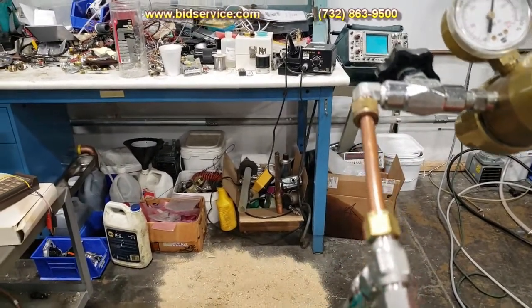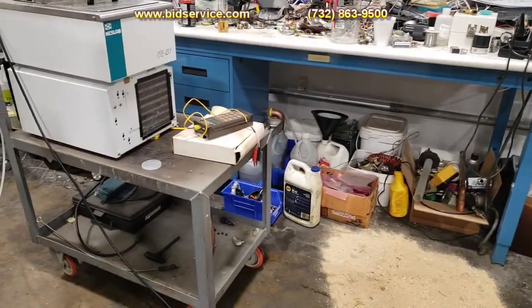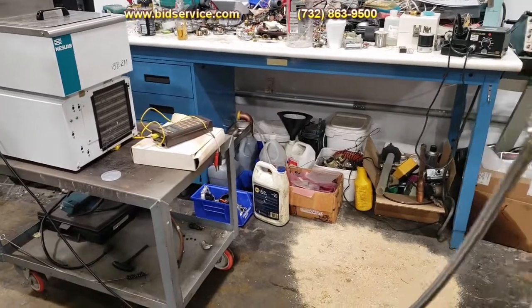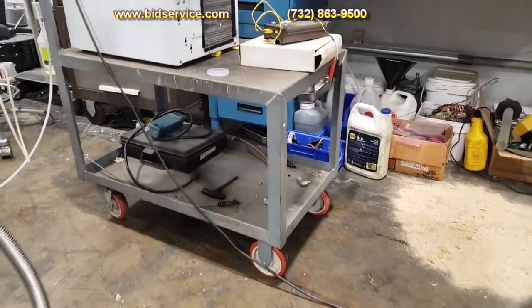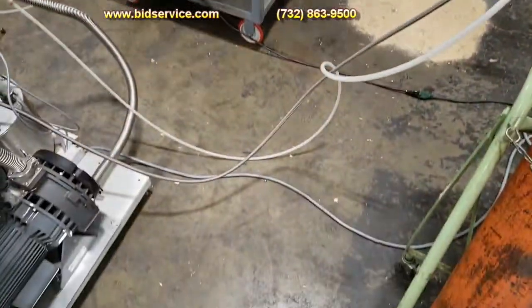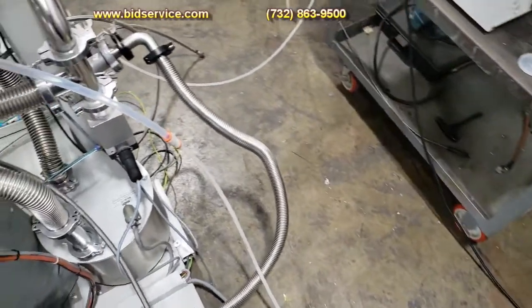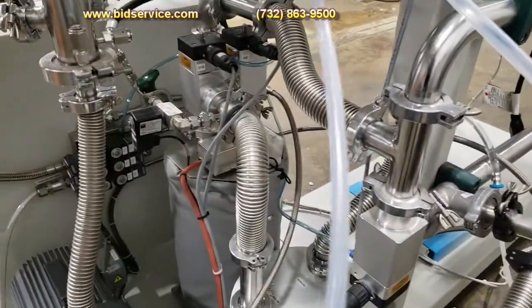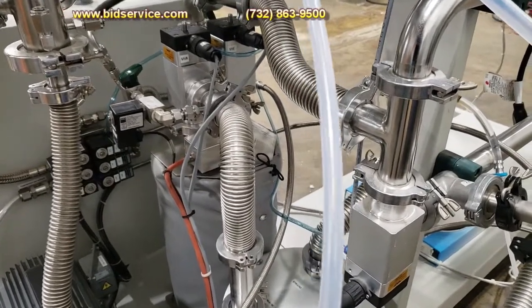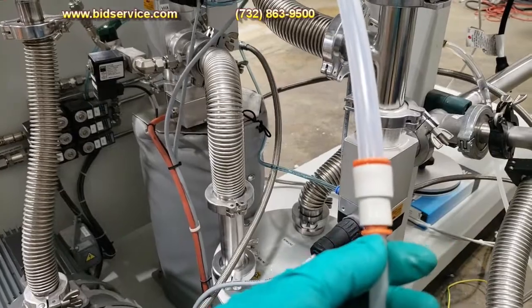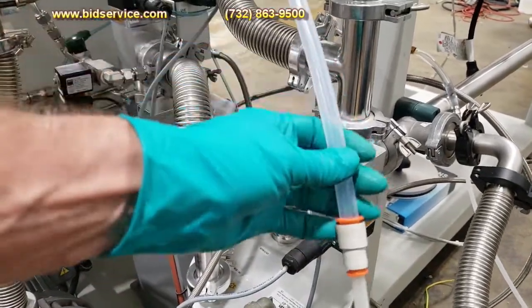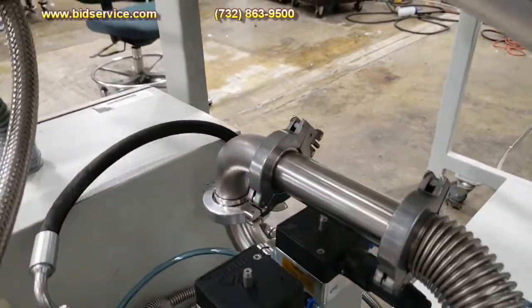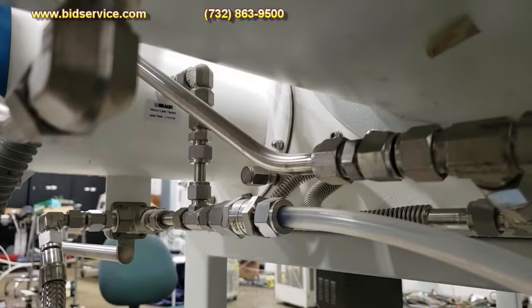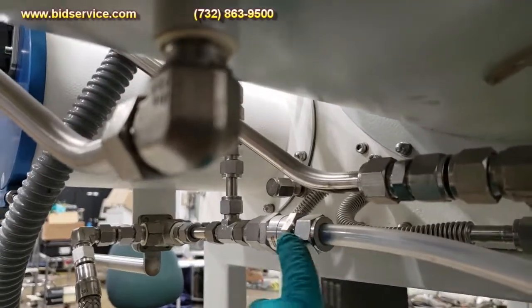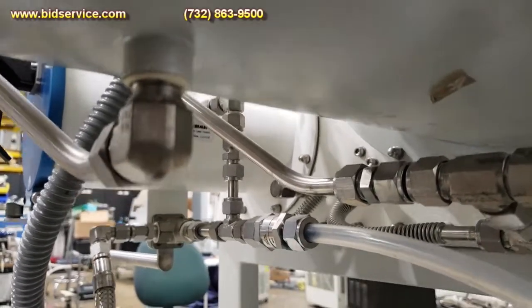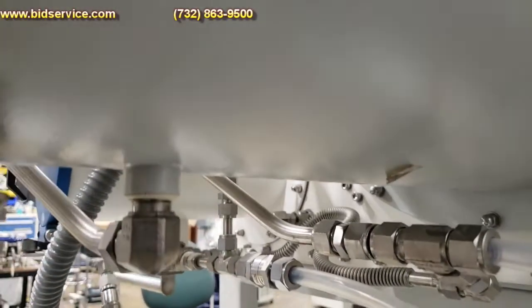I have a T, so your stainless steel line here is your line coming in for your box operation. The other line here is being used for a purge. So when you purge your antechambers, whether it's the small or large antechamber, it's going to come in through here. So when you receive the system, I'm going to disconnect this line off this quick disconnect. This half-inch line here is being set up inside here. This is that line coming in. And it's being used to backfill both your small antechamber as well as your large antechamber.